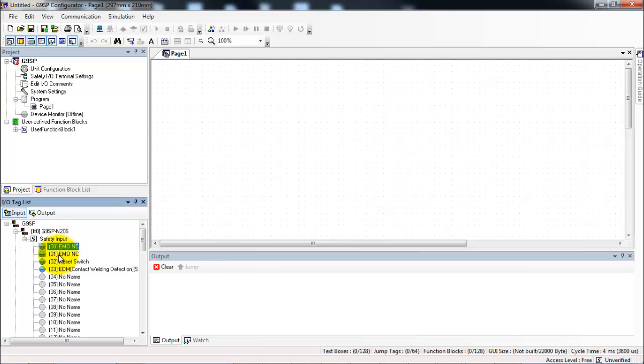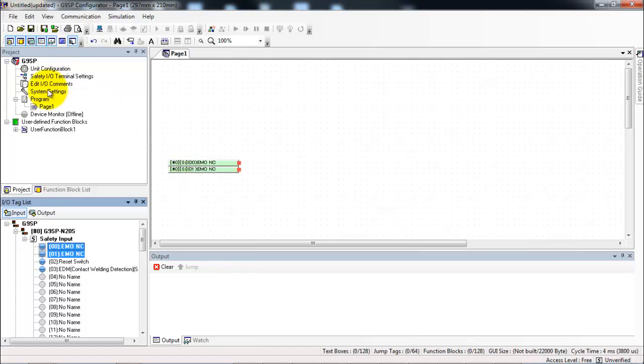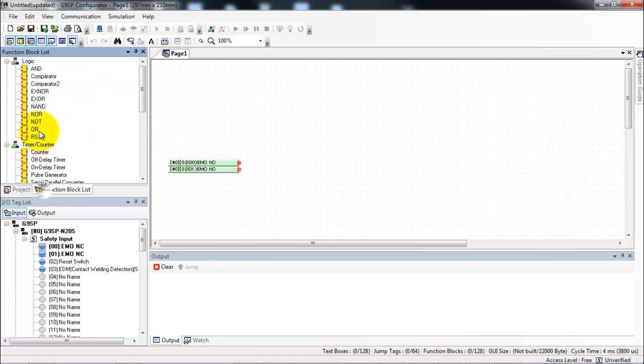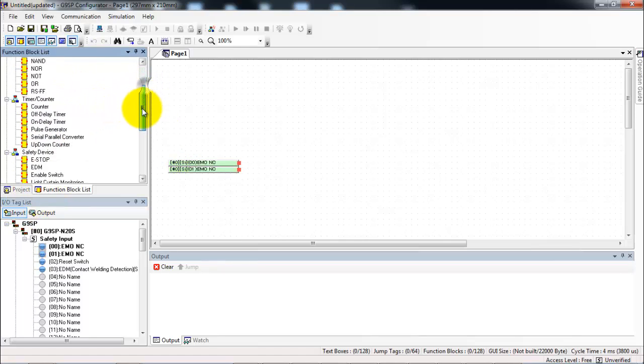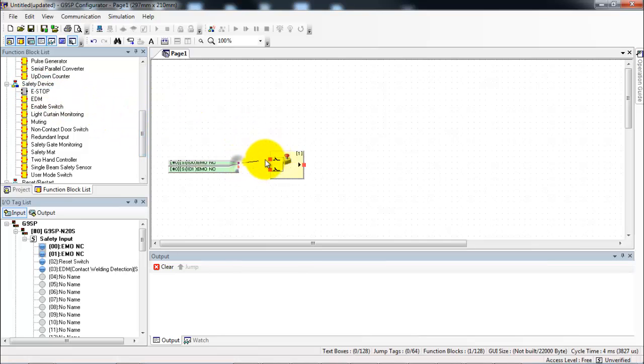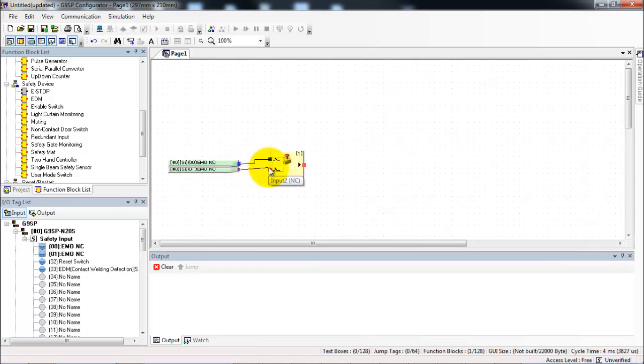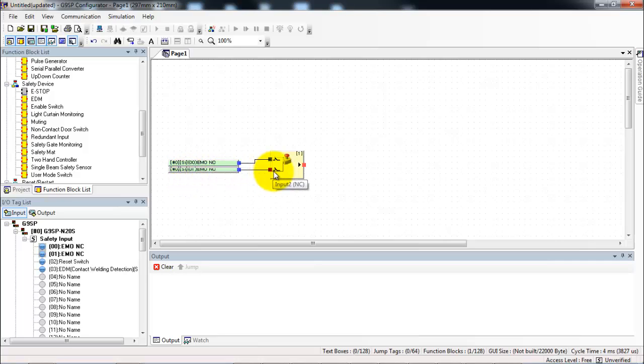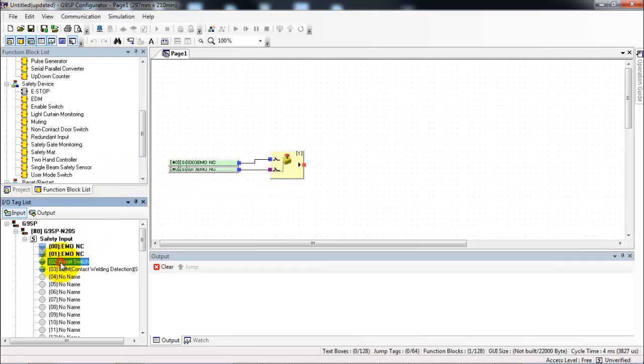So what I'll do first is I'm going to grab my two e-stop inputs, and I'll go to my function block list and grab an e-stop function block. And I just click and drag to make wires between the inputs and the e-stop function block. This function block's purpose is to check for discrepancy errors between the two input channels.